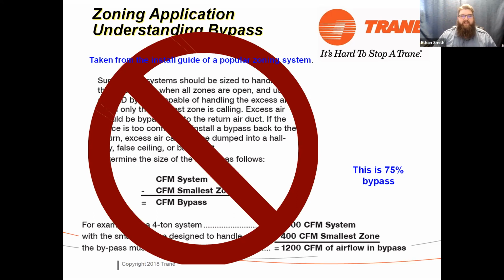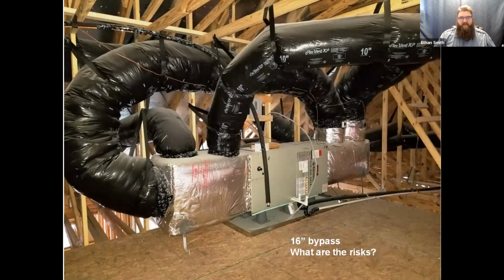Okay. If you're going to have to bypass more than 30%, you're going to have problems. Sometimes you're going to have problems if you have to bypass 30%. Okay. It all kind of depends on your system. But yeah, to have an OEM zoning system tell you that you need to have a 75% bypass capacity, what are we doing? Okay. So hopefully we're dispelling some of those myths. This is an actual zoning system, guys. That's the bypass duct.